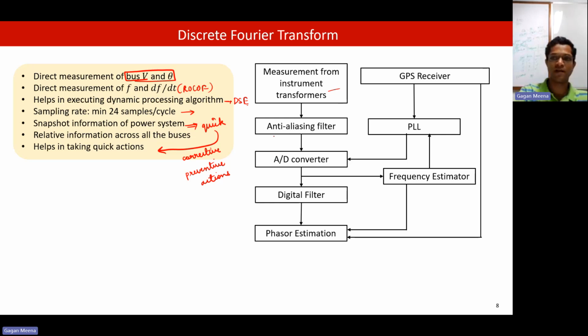This is the entire diagram for the PMU. We have measurements from the instrument transformer, the CT and PT, from which we get the voltage and current signals. We pass them through a filter, then through an analog to digital converter. The analog signal becomes a digital signal, which is passed through a digital filter, giving us our filtered digital signal, and then we do phasor estimation using DFT.